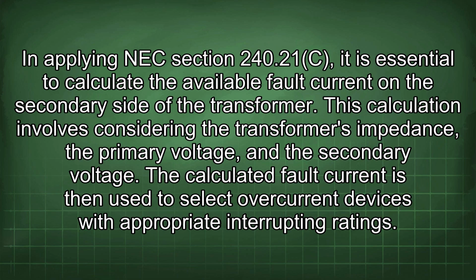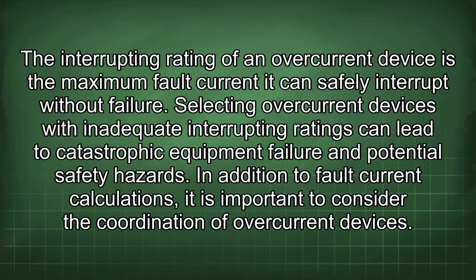In applying NEC Section 240.21(C), it is essential to calculate the available fault current on the secondary side of the transformer. This calculation involves considering the transformer's impedance, the primary voltage, and the secondary voltage. The calculated fault current is then used to select overcurrent devices with appropriate interrupting ratings. The interrupting rating of an overcurrent device is the maximum fault current it can safely interrupt without failure. Selecting overcurrent devices with inadequate interrupting ratings can lead to catastrophic equipment failure and potential safety hazards.